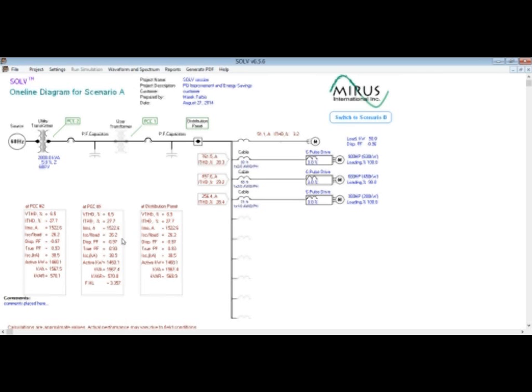Okay, we have another question. IEEE 519 has THDI limits, but is the priority not the THD volts limits? Well, the intention of IEEE is to lower the voltage distortion, and the latest release has made this a little bit easier with the voltage, but the table for the current distortion didn't change. The reason for the current distortion limits is that the actual load is what is causing the voltage distortion. So the main intent is the voltage distortion, but what is causing it is the actual load, which is basically current in the system.